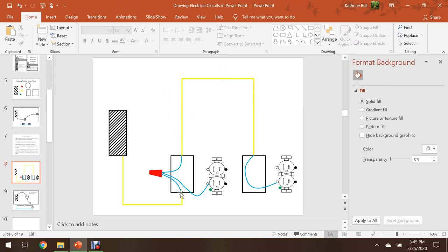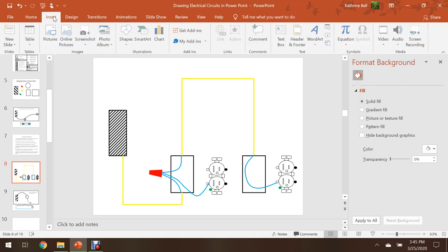All right, we've got to carry our ungrounded conductor or our hot wire. And this time, we're going to use the terminals that are on the duplex receptacle. Now, when I do this, that is wiring this receptacle in series. But as long as that tab that exists right there is intact, then this entire circuit will work. There's nothing in the National Electrical Code that prevents you from using the terminals.